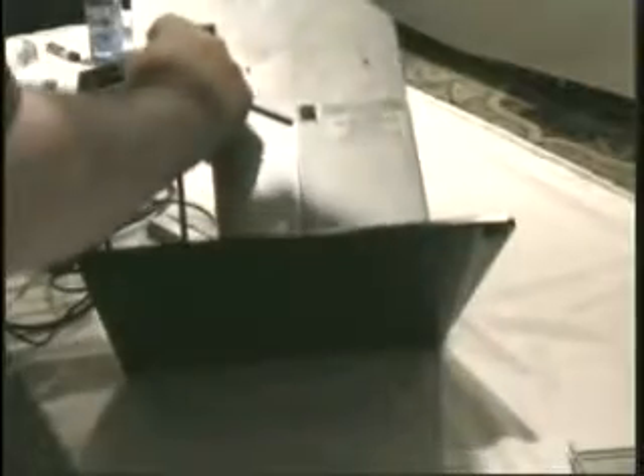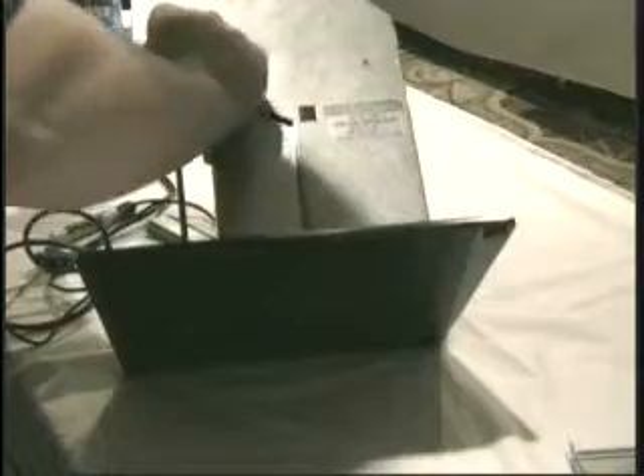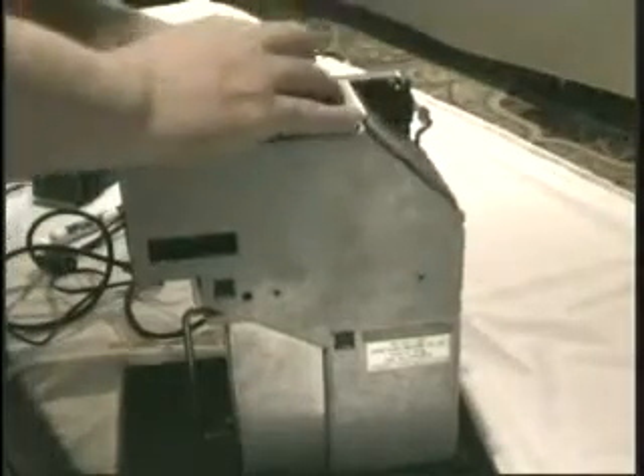Okay, so that's the solenoid. We've checked just about everything mechanically on here that we can. We're down to sensors now, and there are two different tests for sensors. If you look, test 6 is for the head sensors, and test 7 is for the transport sensors.